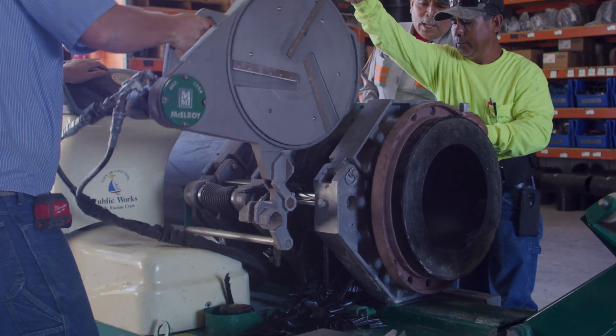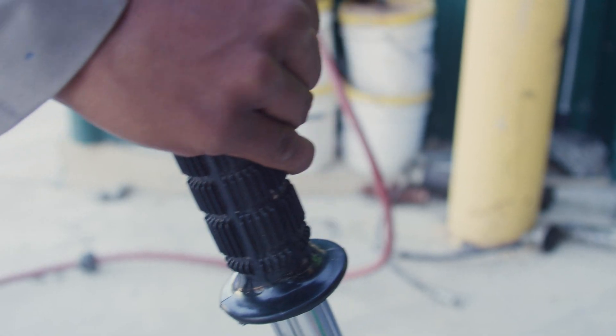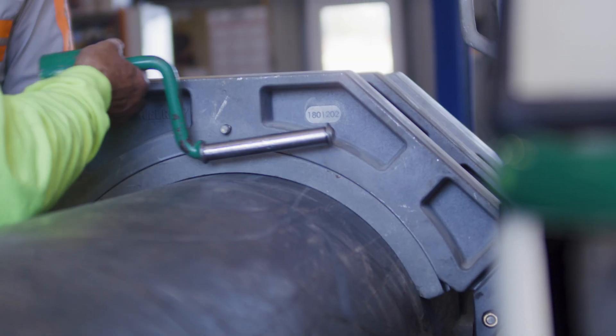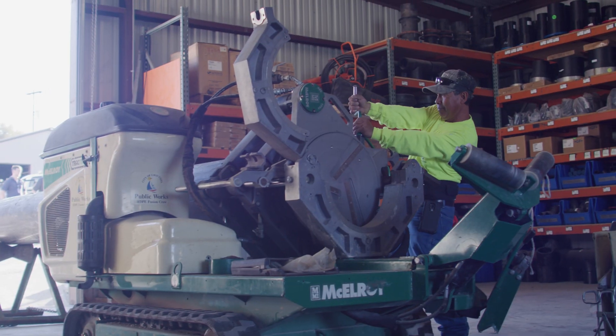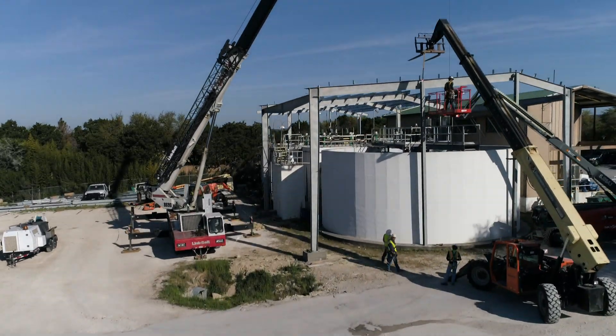We are using HDPE for our water system. We converted over from conventional legacy pipe nine years ago and we've got about 130 miles of HDPE water mains. HDPE pipe is fused together and is a monolithic pipe from valve to valve — it has no joints or gaskets and therefore is leak-free. We also found that HDPE pipe is much easier to install and it's also safer.